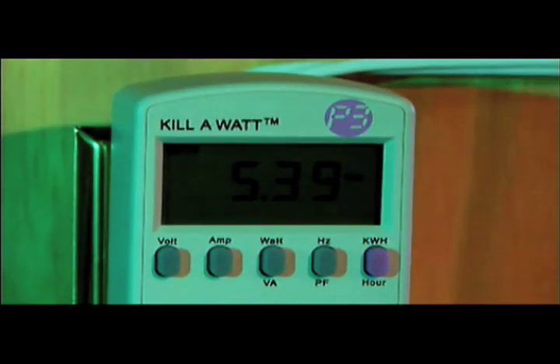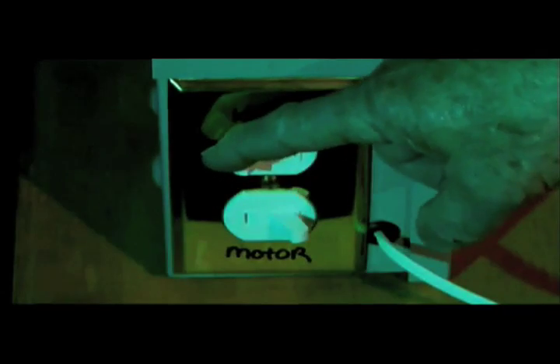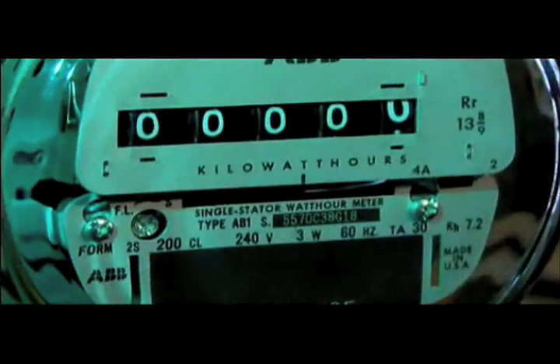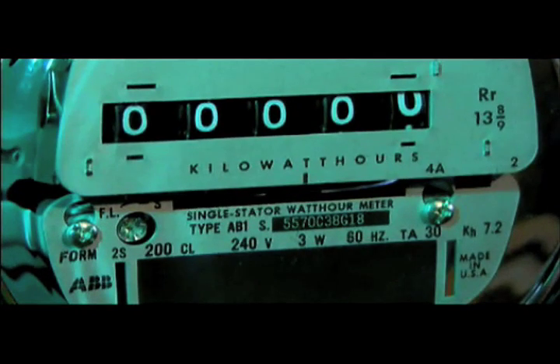As you look at the line coming in at the top of the meter, you have about 5.4 amps. When we turn the KVAR unit on, the amps and the volts going to the motor load don't change. But as you check the amps going back to the source, you can see it drop to 1.5 amps. Whenever you reduce the amps, you remove the heat. You remove the heat, you slow the disc down in the meter. That's money in your pocket when you use the KVAR unit.